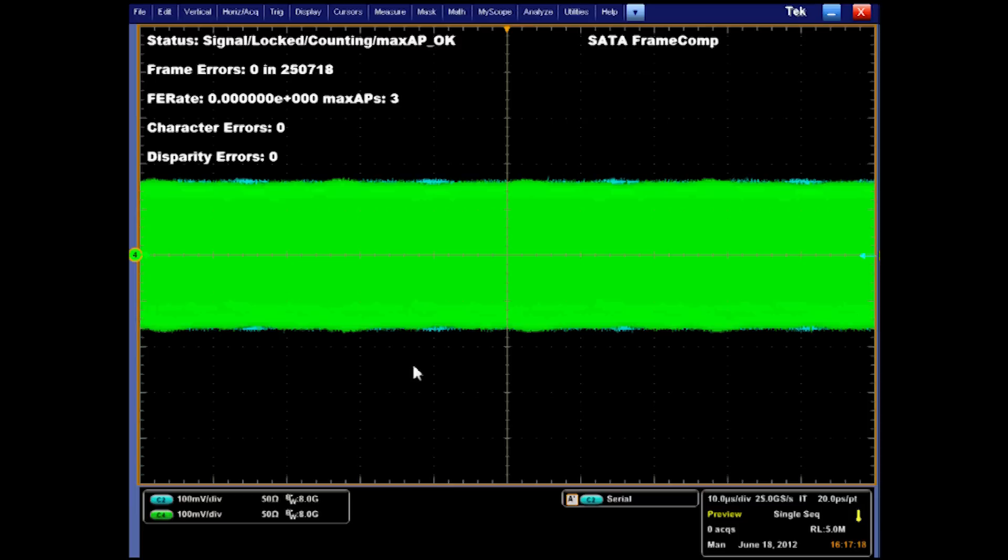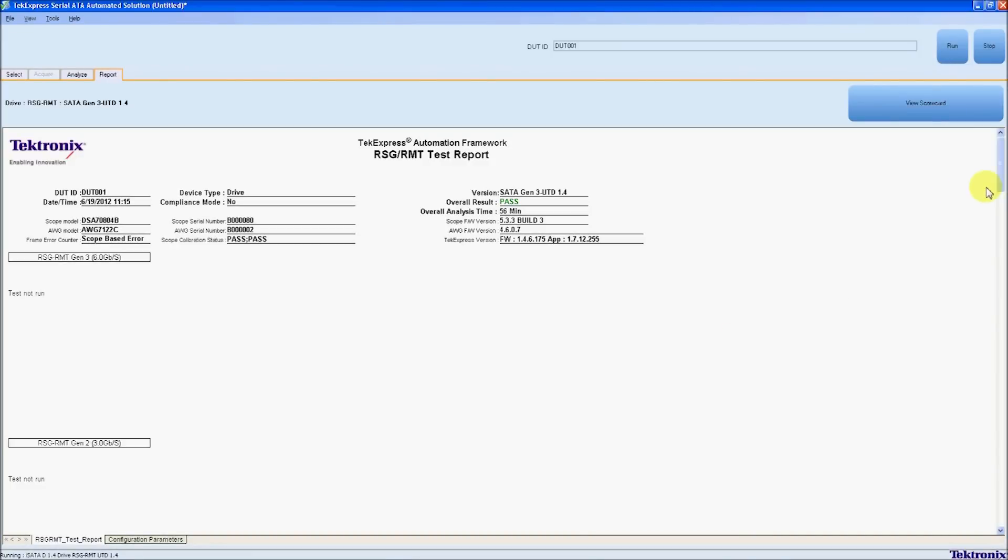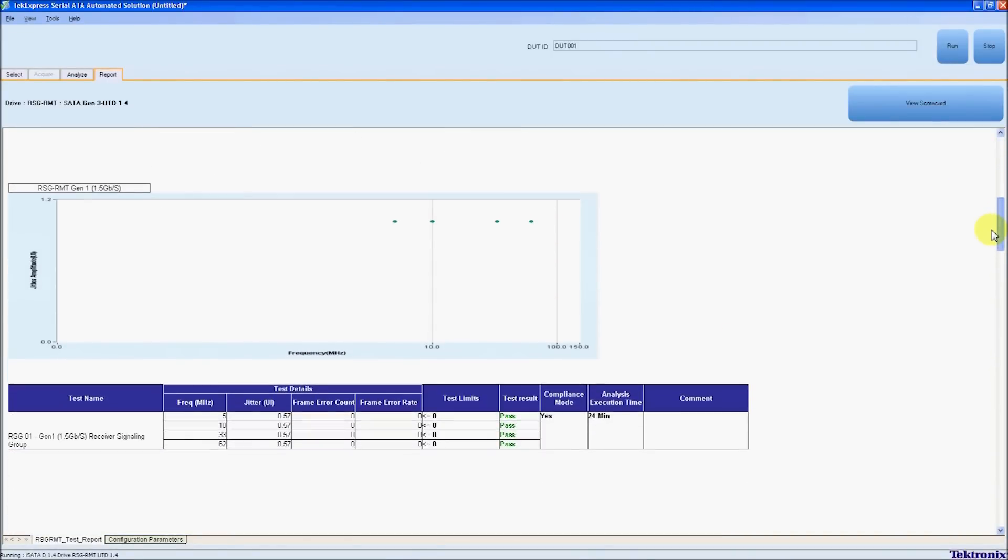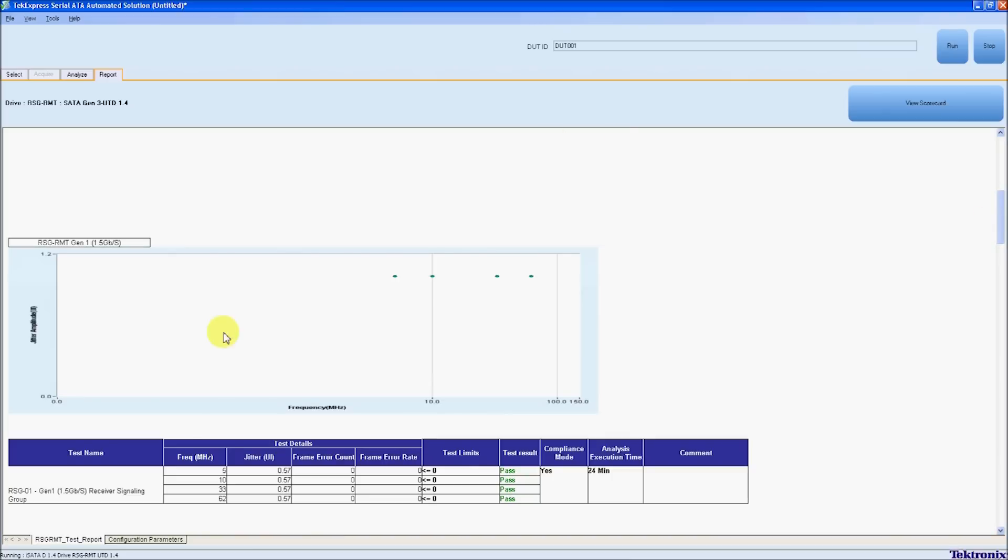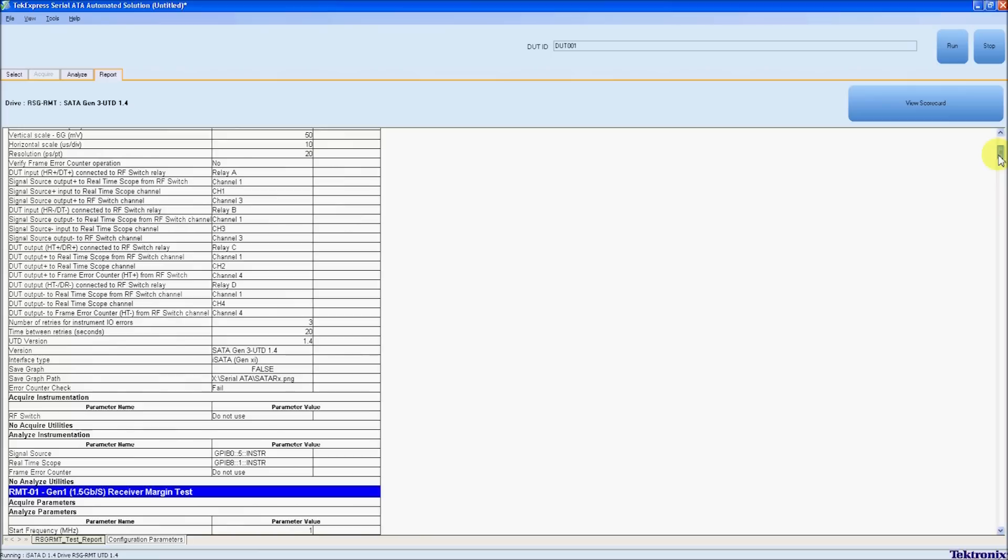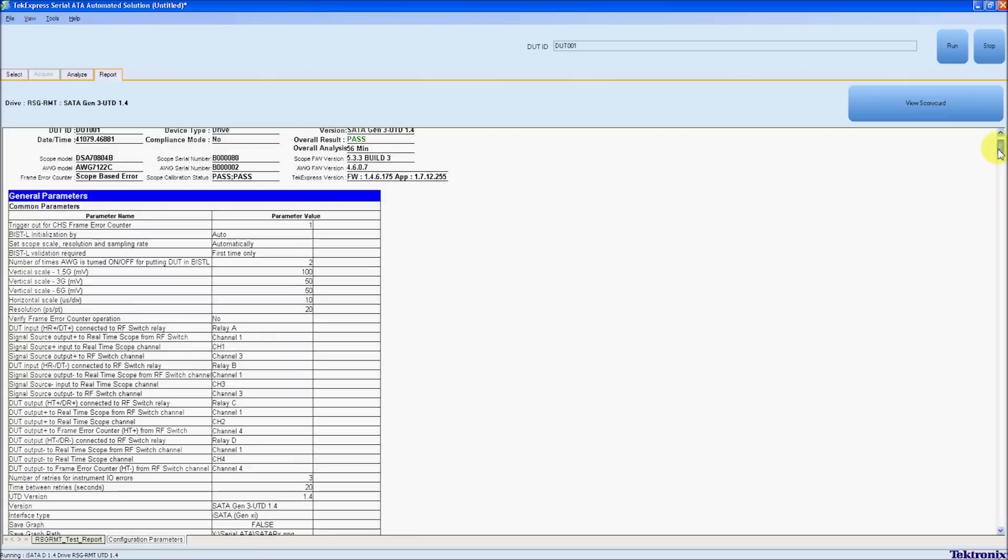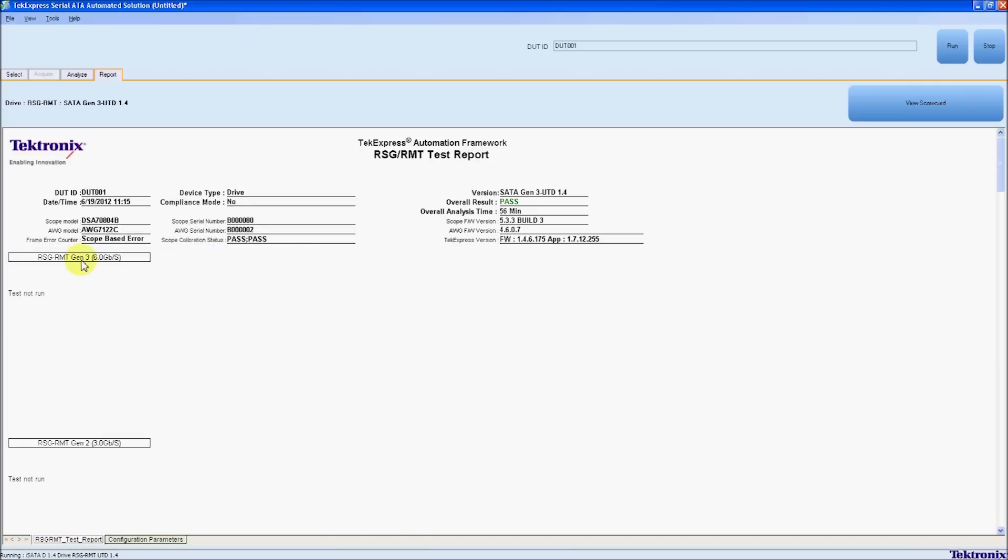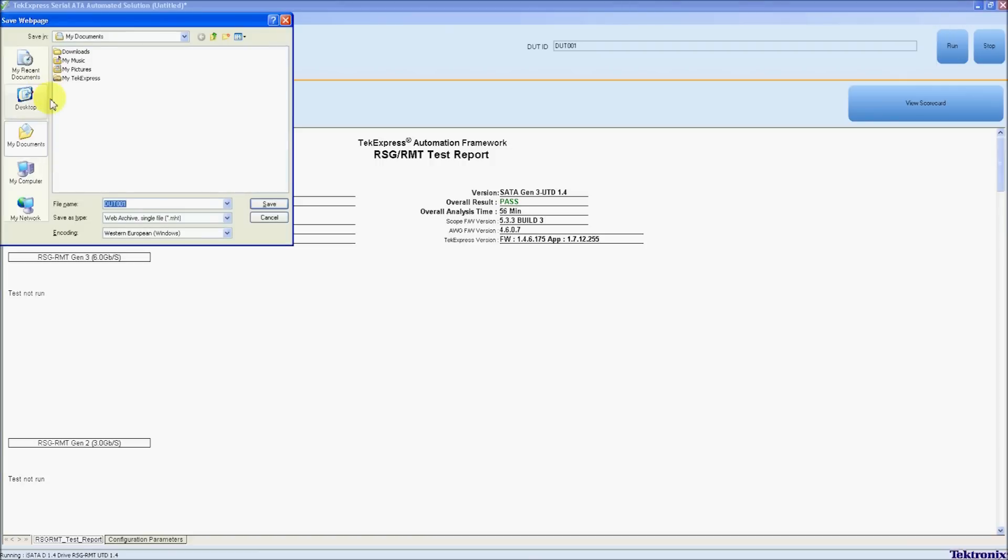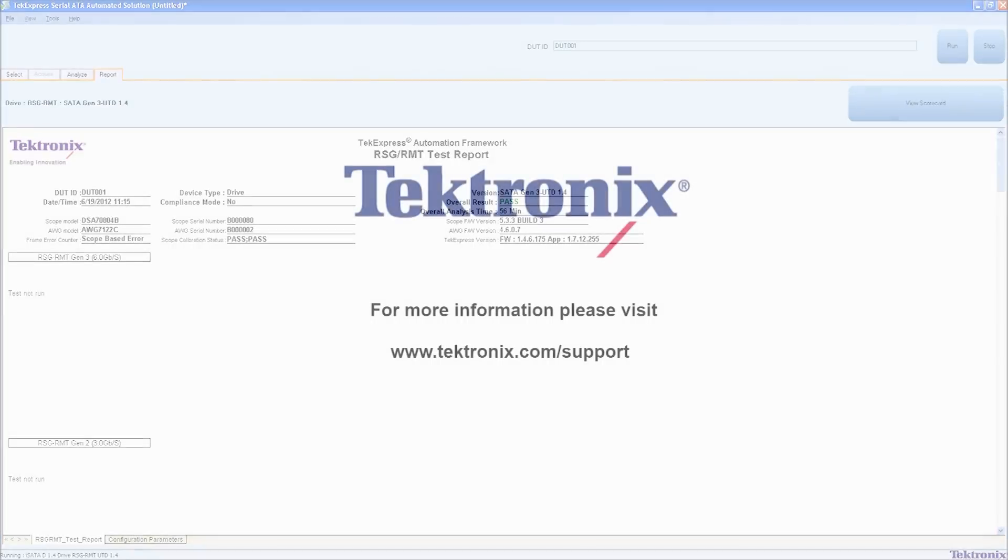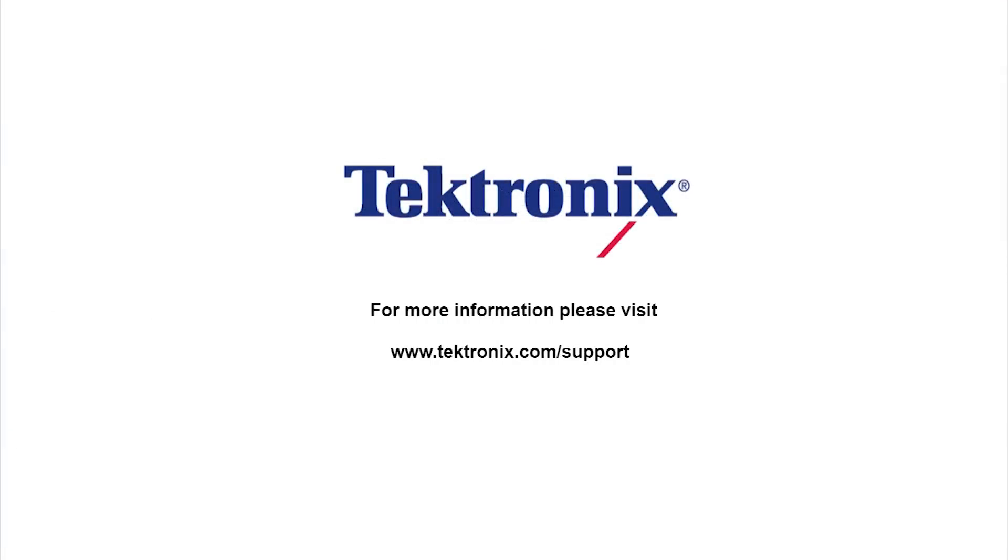Once the test completes, you'll be brought back to the TekExpress window where you'll be able to view your scorecard and your jitter and amplitude measurements. There's also a tab at the bottom that allows you to see all the pre-configured settings, as well as firmware versions, scope used, serial numbers, and such. From the main one, you can go up to File and select Save. This allows you to save this as an MHT. This file can be opened in Internet Explorer for later use. This is SATA testing, and if you have any other questions, please contact us at www.tektronix.com/support.